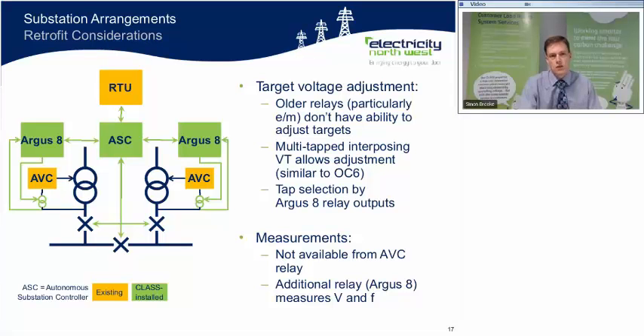And so in these substations, we use additional Argus 8 relays, which have two functions. The first is that they carry out the voltage and frequency measurements that we require. And the second, we use the output relays to adjust the tap on a multi-tap interposing VT, which we show here. And what these interposing VTs do is they adjust the voltage seen by the AVC relays to fool them into effectively moving their voltage set point.